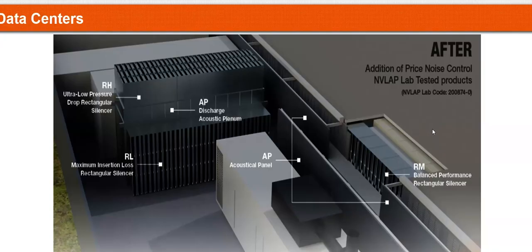Those servers also emit a very particular frequency that can be disruptive to residents. So the silencers and the catwalk are multi-purpose: for the sound coming in from outdoor equipment into the offices in there, but also for the hot aisles in the server rooms, that high frequency noise coming through openings towards residences around. There is no quick, cheap solution that fits all. The cheapest solution is to do it at the design stage by using that scientific approach, using tested data, looking at the structural, CFD, and your acoustic analysis recommendations.